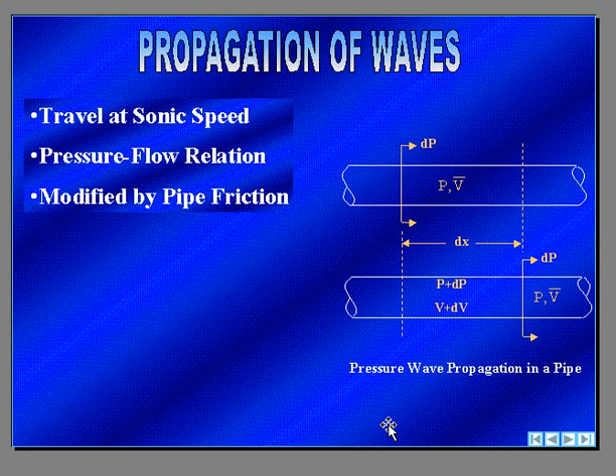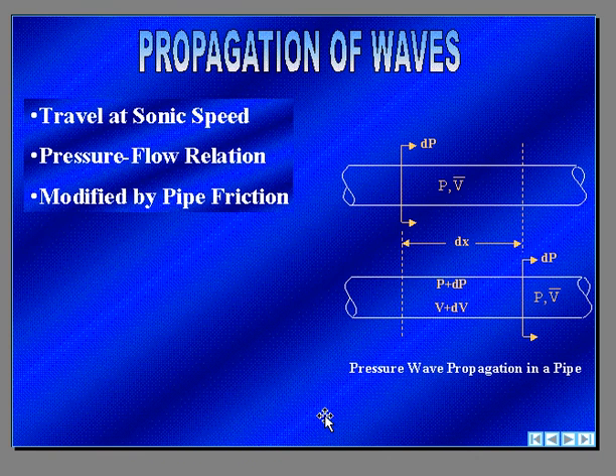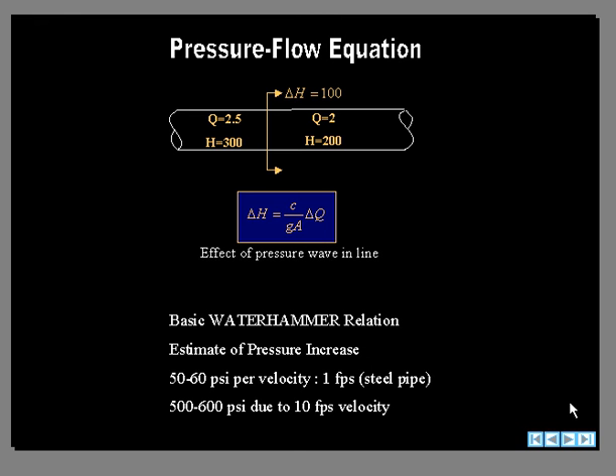Some of the key equations that we use, a pressure wave, of course, travels at sonic speed, and it changes the pressure by amount delta p, and the velocity by the amount delta v. This very simple equation relates the pressure change in feet head to the flow change. The constant is wave speed over ga. And since wave speed is pretty high, this is a fairly large number.